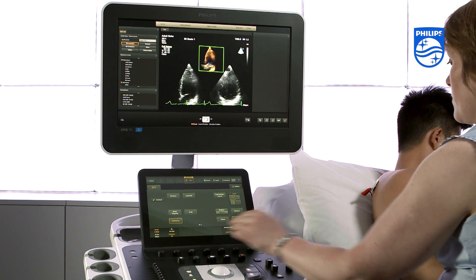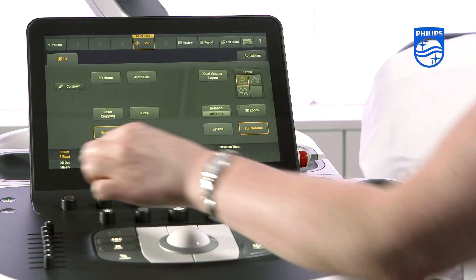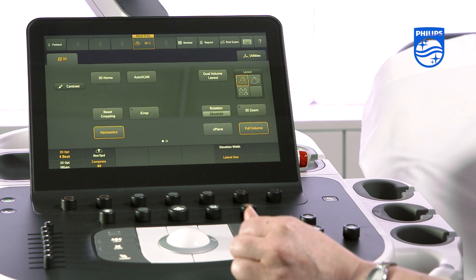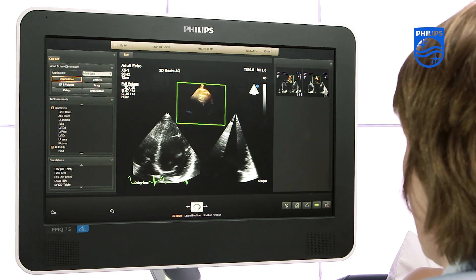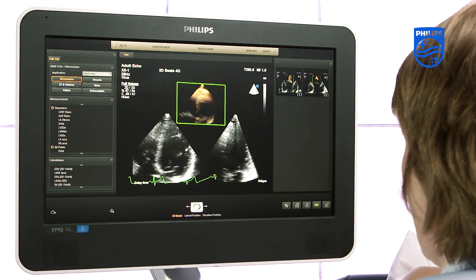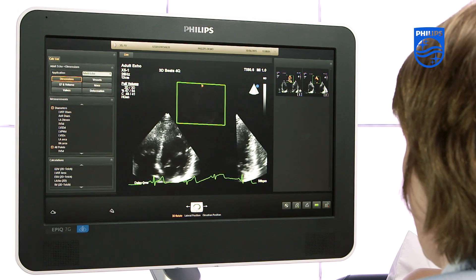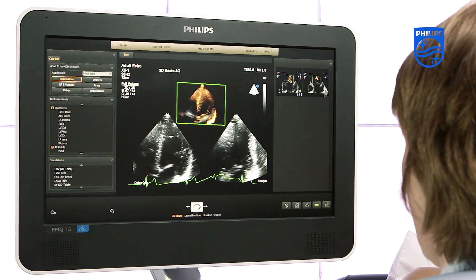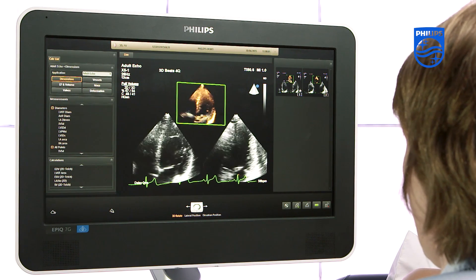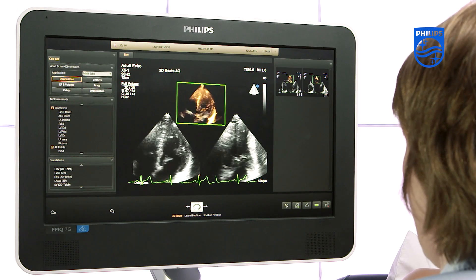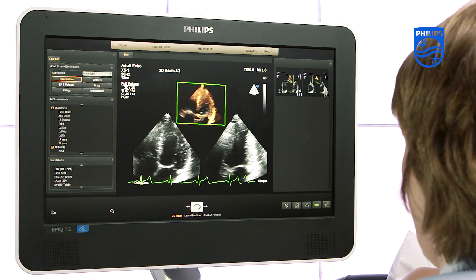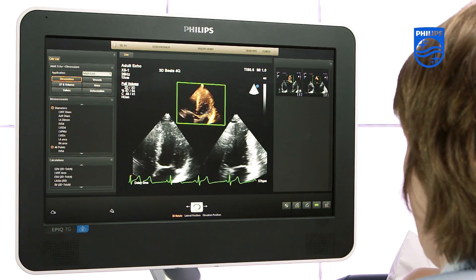Then turn the 3D op control beats to 4. You will now see the system combining the four sub-volumes over the next few seconds, and once they have combined that process goes on continuously. You can then press acquire or freeze at any time.